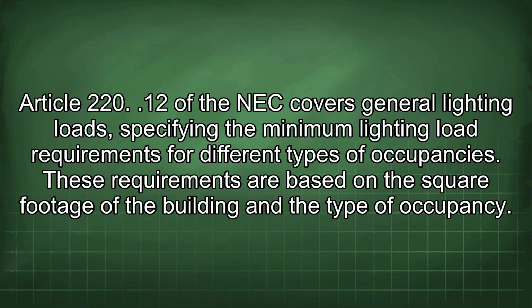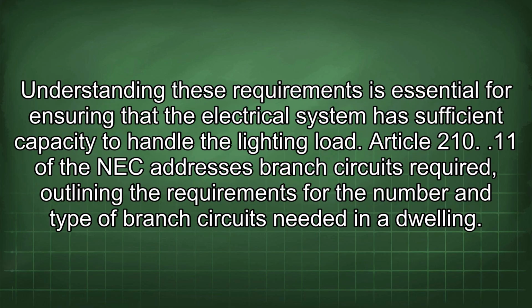Article 220.12 of the NEC covers general lighting loads, specifying the minimum lighting load requirements for different types of occupancies. These requirements are based on the square footage of the building and the type of occupancy. Understanding these requirements is essential for ensuring the electrical system has sufficient capacity to handle the lighting load.